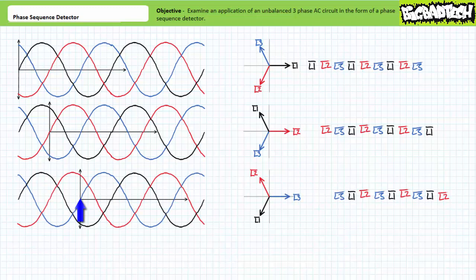Finally, consider L3 in blue as the reference. Represented as phasor equivalents with phase L3 assumed to be the reference, L3 in blue would be 120 volts at an angle of zero degrees, L1 in black would be 120 volts at an angle of negative 120 degrees, and L2 in red would be 120 volts at an angle of 120 degrees. Given L3 is established as our frame of reference, we can state L3 peaks, then L1, then L2. The sequence would again repeat itself: L3, L1, L2. The choice of reference has not changed the phase sequence, only the starting point within the same sequence.